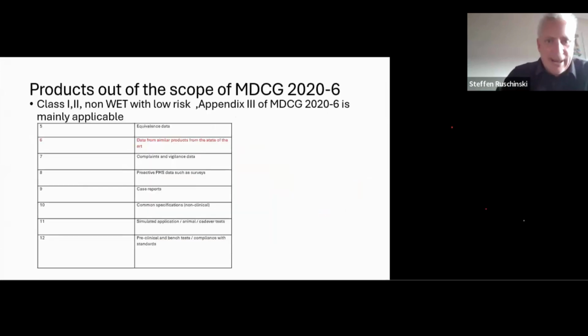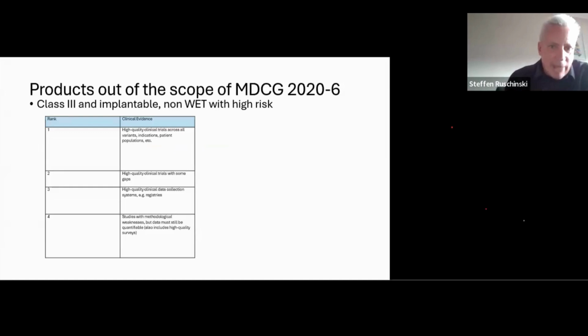What about products that are out of the scope of the MDCG, meaning class 1 to non-WET with low risks? So for them, still Appendix 3 of MDCG 2020-6 is mainly applicable, meaning we can use a combination of clinical data from 6 to 12, but not from 5 to 12, sorry, but not 6, meaning the similar products from the state of the art. Class 3, and implantable non-WET devices with high risks always have to get a combination of ranks 1 to 4.